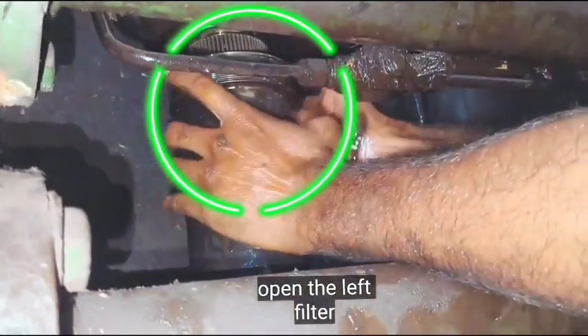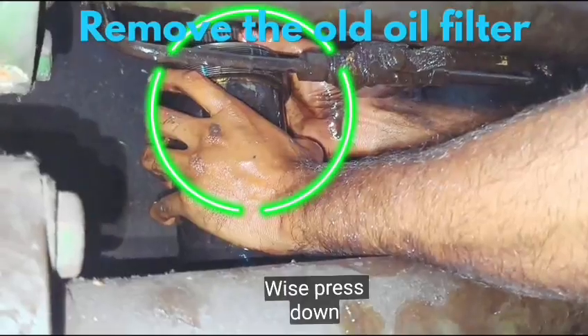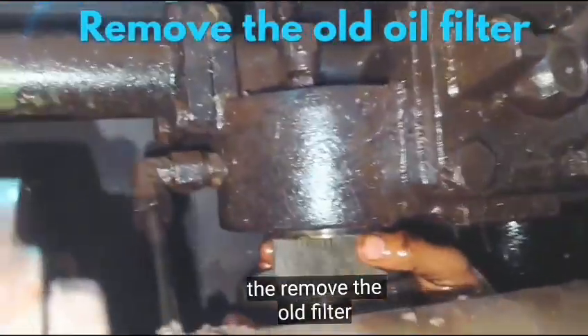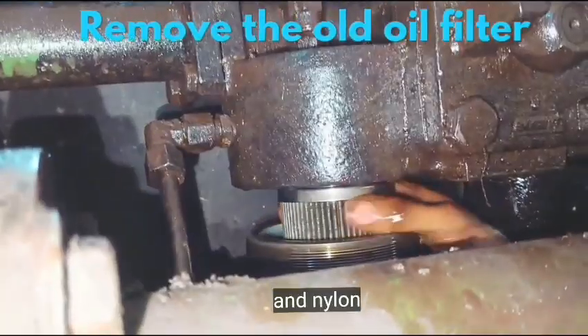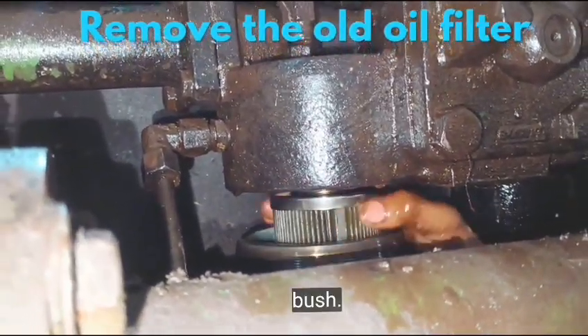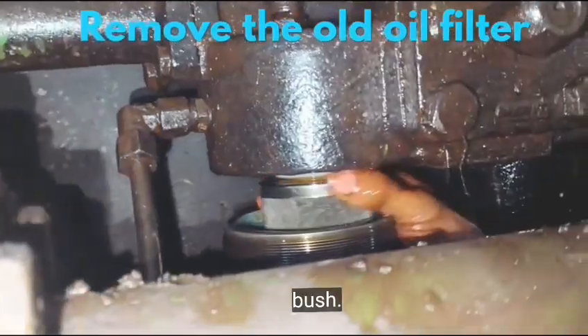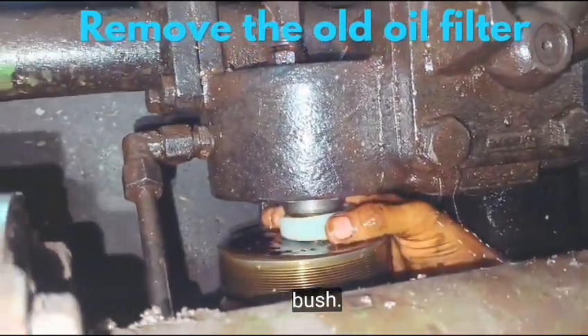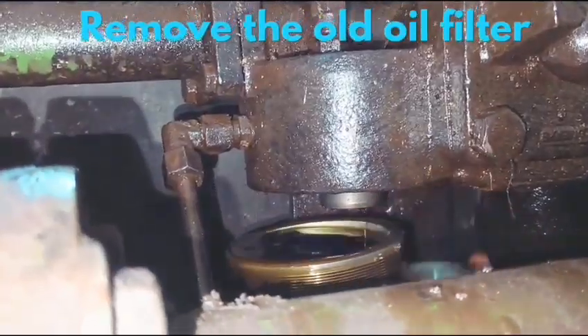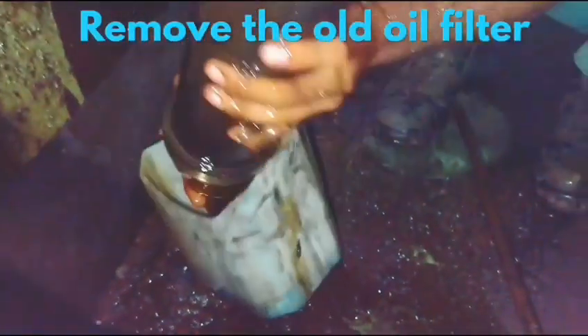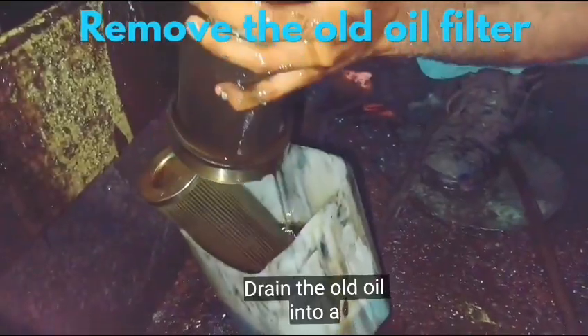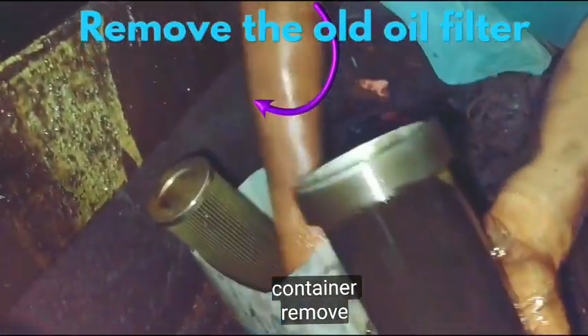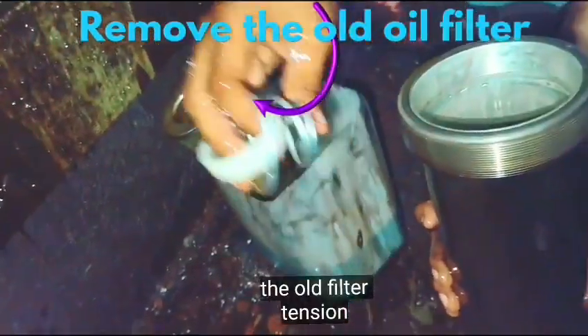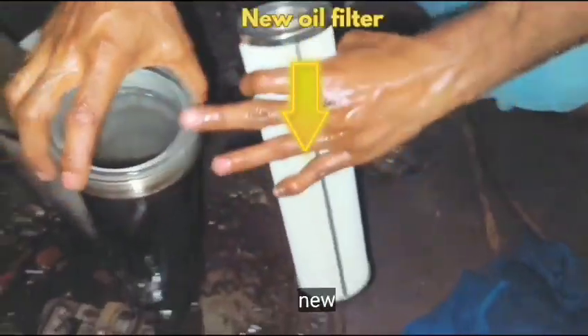Left side filter replacement. Open the left filter housing anti-clockwise. Press down to remove the old filter and nylon bush. Drain the old oil into a container. Remove the old filter, tension spring and nylon bush. Take a new filter.